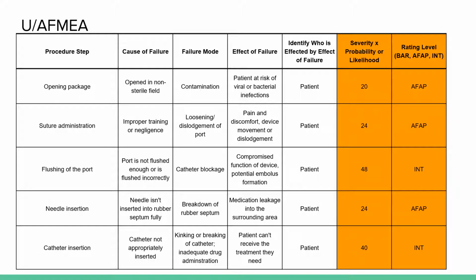So then we did a UFMEA analysis, which looks at the failure modes from a user standpoint. From this, many of the failures occur within the patient. For example, if the sutures aren't implemented correctly, the sutures won't be attached to the port, and the sutures could be dangling from the port. Also, if the port isn't flushed correctly or not on a regular basis, it could lead to potential death of the patient due to blood clots building up in the veins.